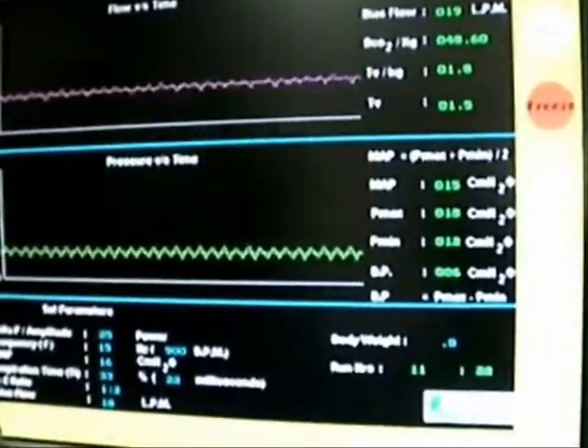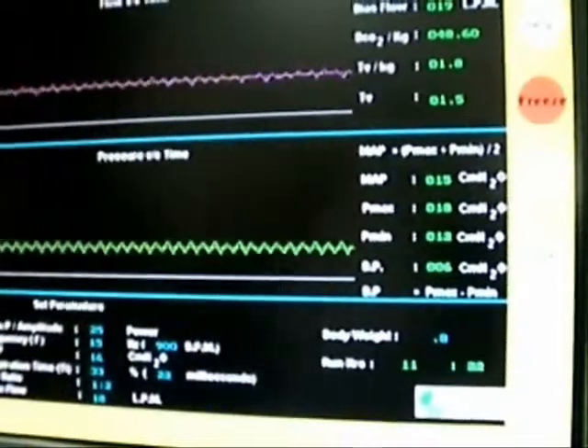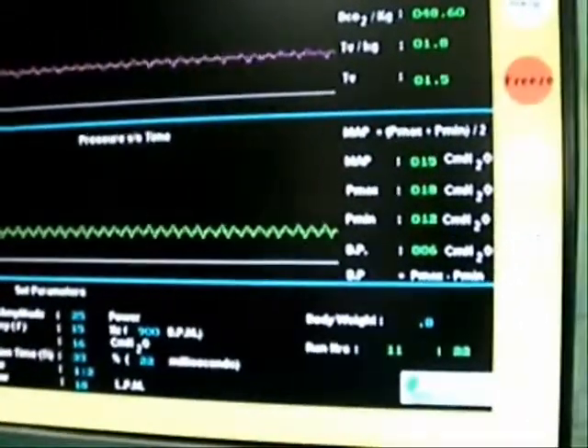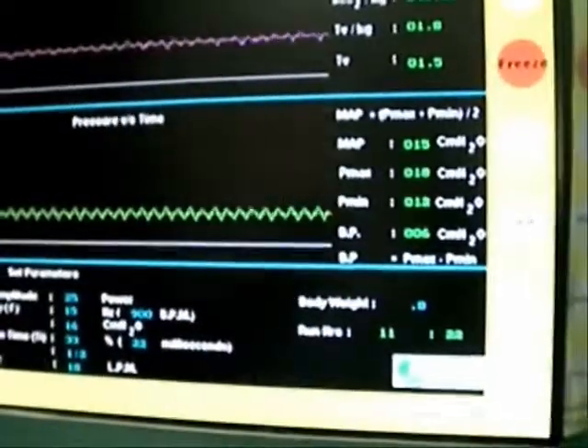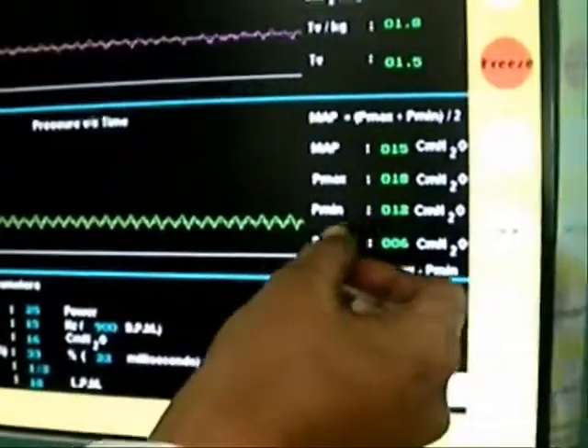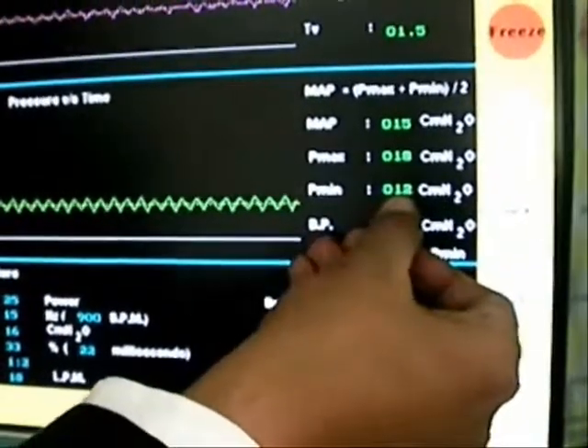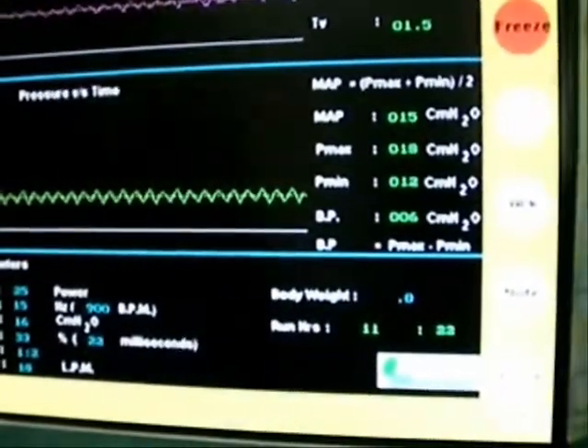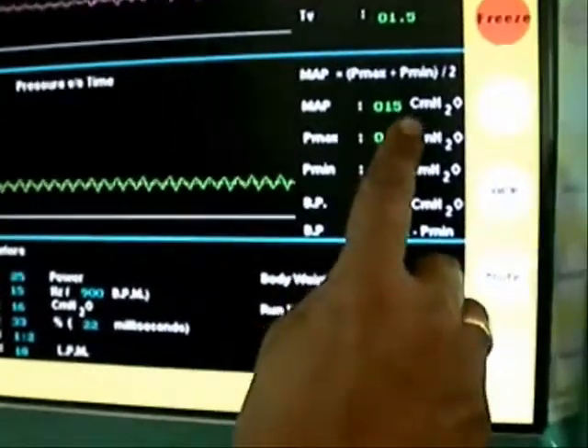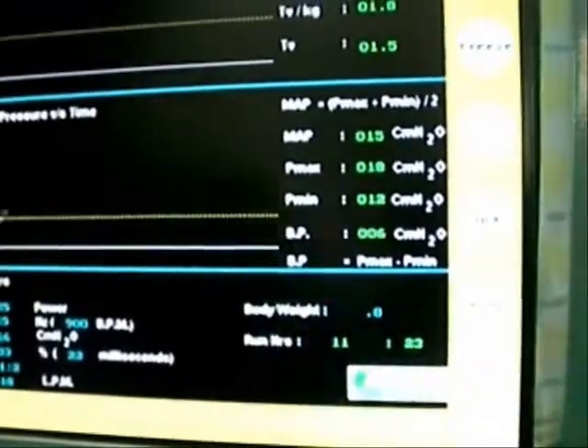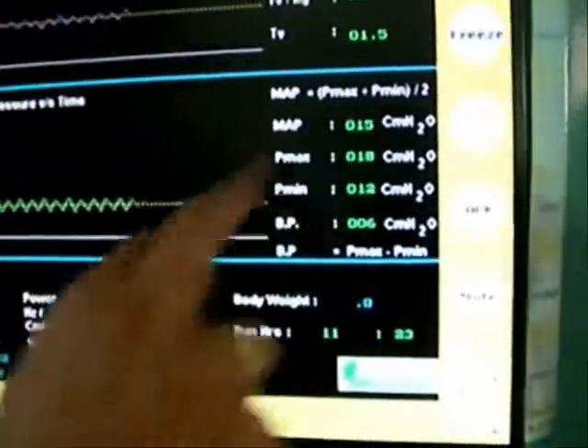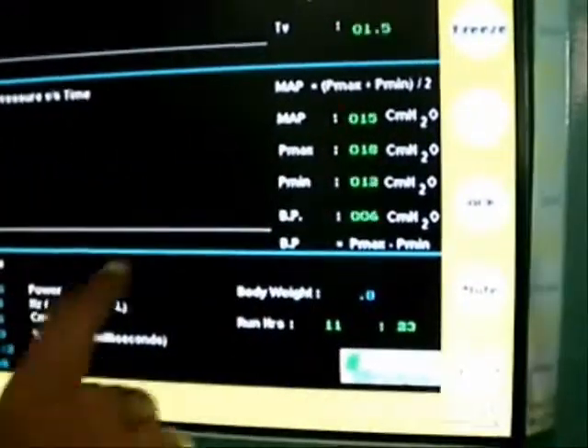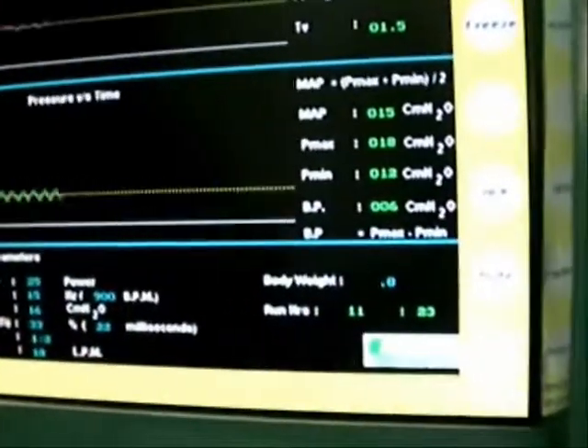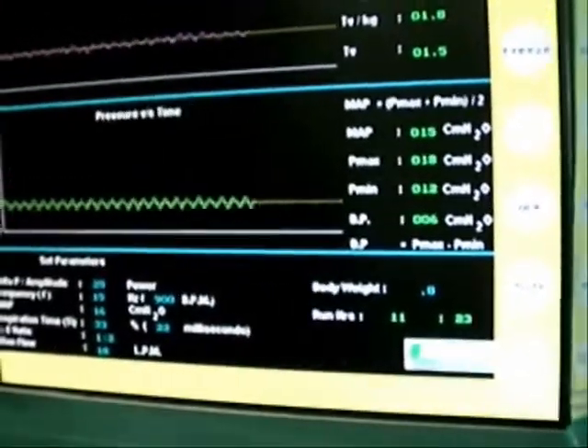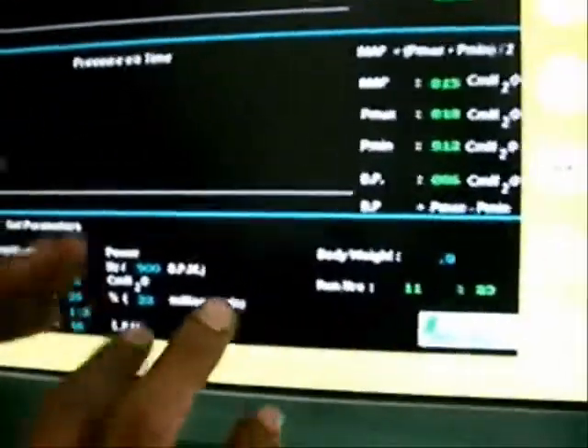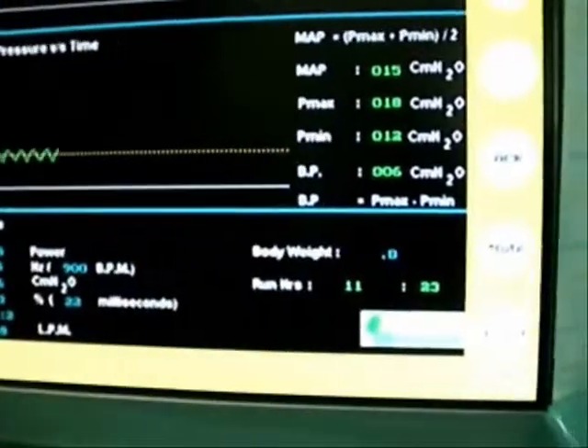Simultaneously, during the expiratory phase, when the piston comes back and sucks the air from the patient's airways, a negative pressure is created in the airways. That is again sensed by the pressure sensor and indicated as the P minimum. So here it's 12. So how do we calculate the MAP? P max plus P minimum. So here 18 plus 12 is 30, divided by 2 is the mean airway pressure. The set mean airway pressure and the delivered mean airway pressure match within an accuracy of plus or minus 1 centimeter of water column. And here you have the differential pressure. That's the true amplitude actually.